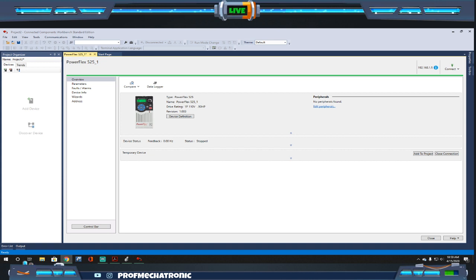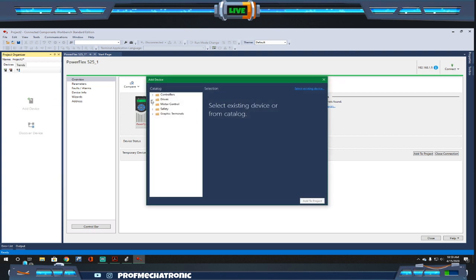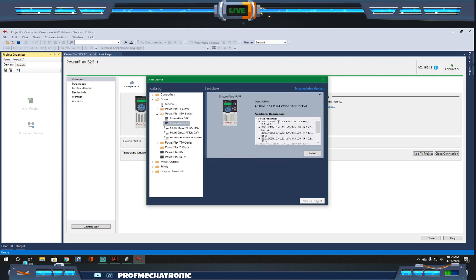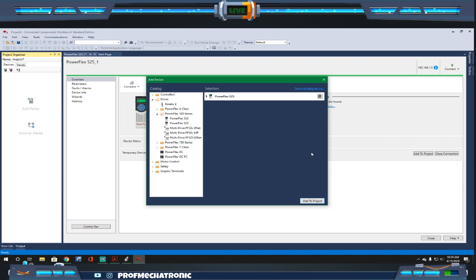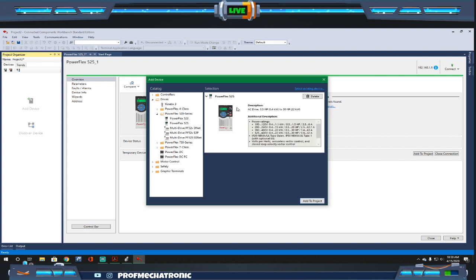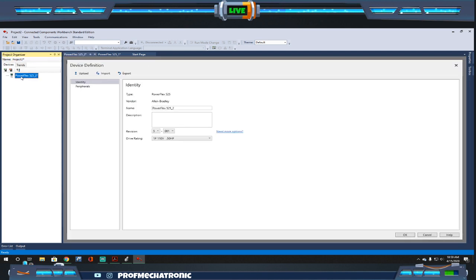All that kind of stuff. Connected Components Workbench I've used extensively when doing offline setup. Before I actually go to the field for a job, I'll add devices to my project tree. From here, you can add a drive, add a 520 series, add a 525, pick the drive you want—that's the select. I'll select that drive and add it to the project. Now the drive's added to the project, and I can select the revisions.